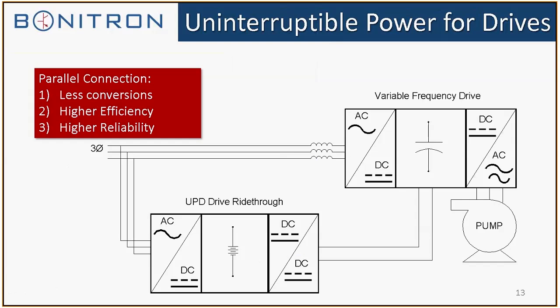This is Bonitron's topology. We're parallel to the drive. We don't affect the process during normal operation. We connect to the DC bus with one single conversion, AC to DC. Regardless of which ride-through you're using, it's always just one single conversion. Either you're taking the AC line in the sag and using the remaining AC line and boosting it directly into the DC bus, or you're pulling out of an energy storage device like capacitors and batteries.